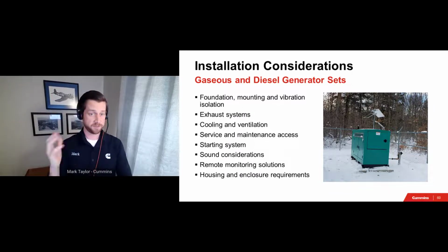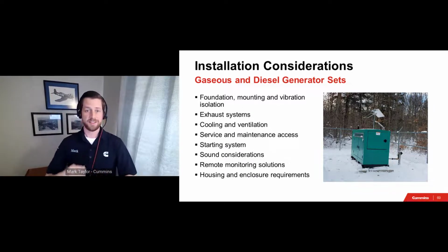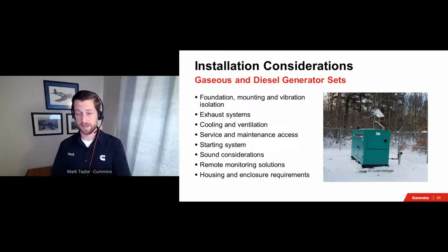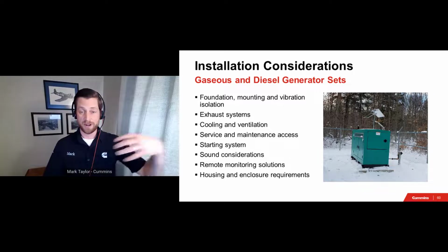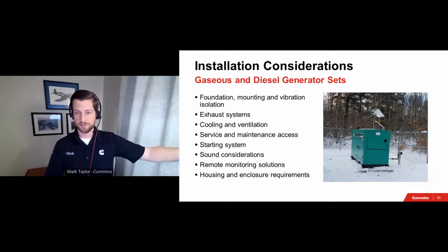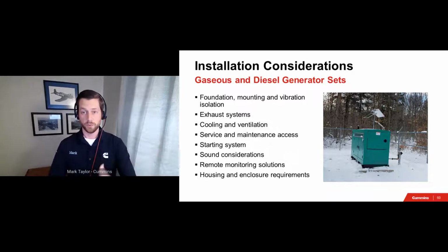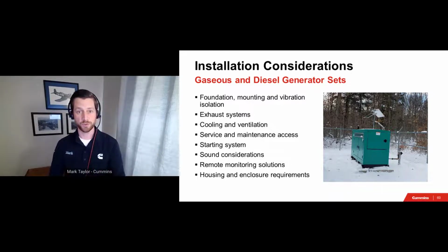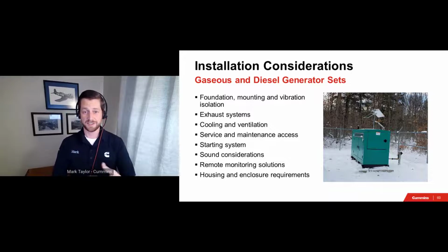Both are powered by a reciprocating internal combustion engine and as such produce vibrations that may need to be accommodated with proper mounting, such as a proper foundation or anti-vibration mounts when necessary. Exhaust system routing designs for both generator sets are also no different. Key concerns being the proper routing, muffler sizing, termination, routing through walls appropriately, and cooling system design and sizing as well. Having proper airflow, proper cooling, it's not really any different. The starting systems, especially the batteries, those are the same.